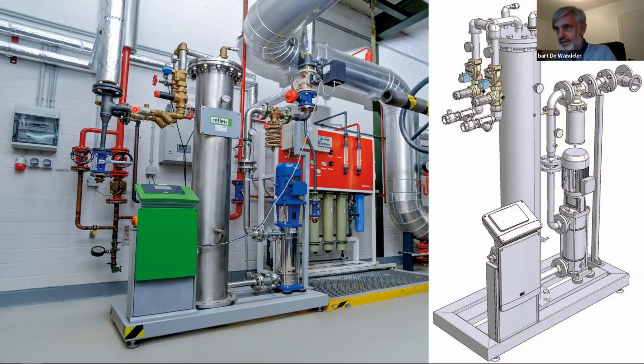We also have a big line to do automatic water makeup. We first degas the water, pump it through, and give it back to the system. Here we even have two separate systems, each its own line, with actuators between them. So when one system is running, we degas and protect that system. When it's in shut-off mode and we run the other system, this valve closes and we degas the other one instead.